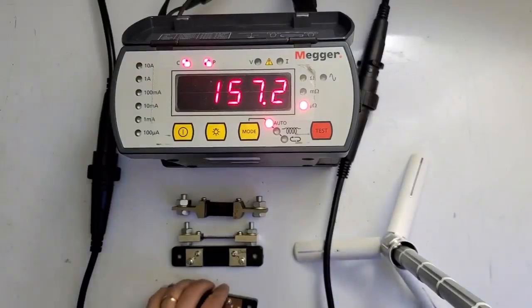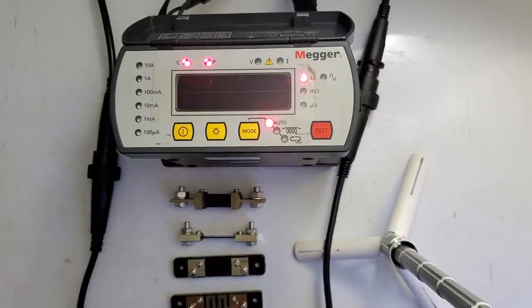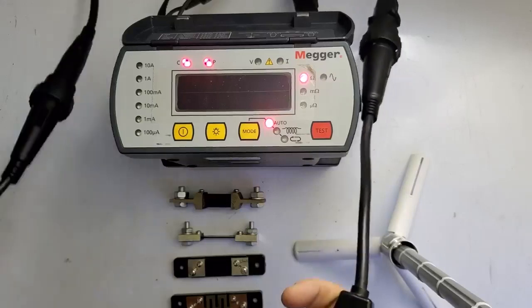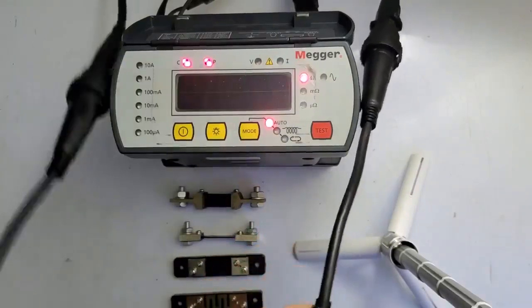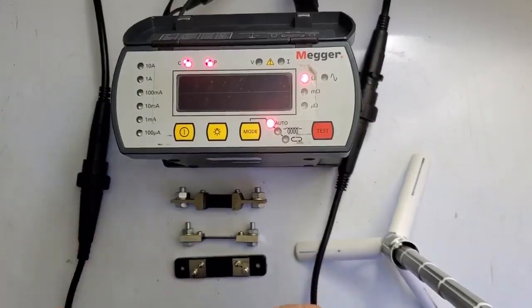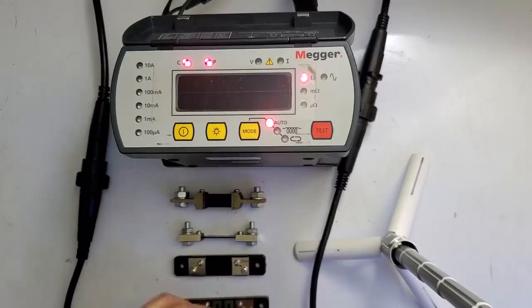Alright guys, today I want to do another demonstration on what to expect and how to do self-checks for your equipment. This is a Megger DLRO10 — any DLRO will work, but I'm using the 10 with the standard manufacturer leads. I have it set to auto. For a DLRO, the best way to do a quick, expedient self-check is to use a dead short and then some kind of known resistance, if you have that available.